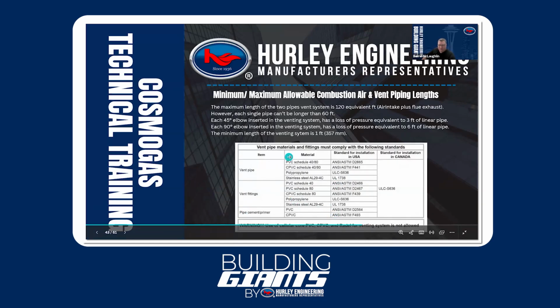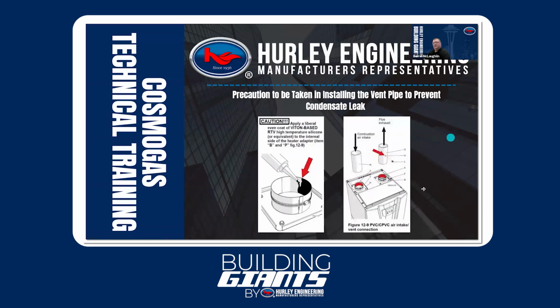So one thing I want to note here, let me get to the next page. Yes, so the exhaust and intake here, these fittings on top are meant to accept different sizes because you're going to have different diameters of PVC, CPVC. They're not meant to seal from moisture. So when you install these, if you don't put the RTV in here, you have not sealed for moisture and you will leak condensate into the room. You have to use the RTV sealant to get that watertight seal.